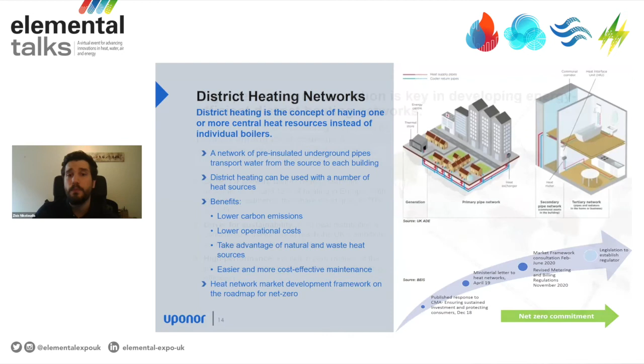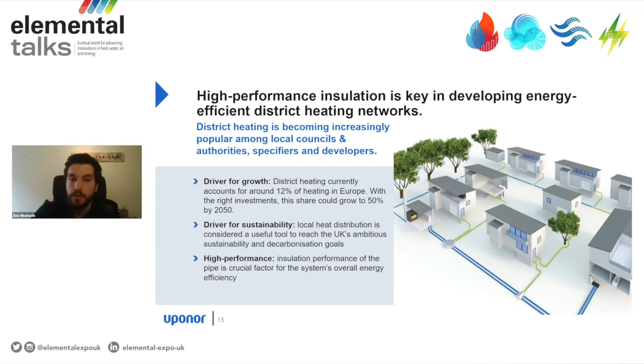So therefore, we can understand that there is a direct driver for growth for district heating networks in the UK, which actually is a driver for sustainability on the road to meeting the decarbonization goals that the UK government has set. What we need to keep in mind is that one of the most important things that can play a vital role in designing and developing highly efficient district heating networks is the insulation of the pipework that carries the water from the energy center to the building. Not only because this can affect the water temperature delivered to the building, but it can also highly affect the return temperature of the water to the energy center, which can have a massive impact on the performance of the energy source.